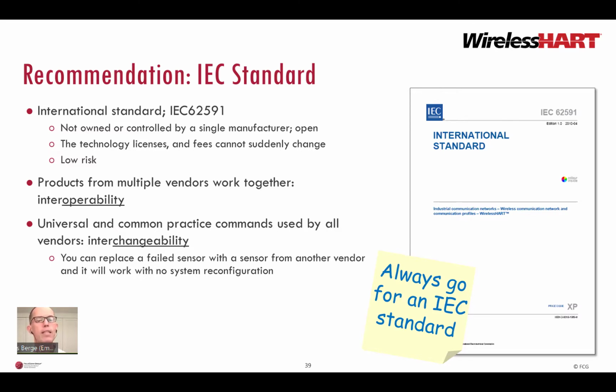Standardization dramatically reduces the risks associated with the technology. This is why I&C engineers specify IEC standards for all electrical and electronic equipment, including telecommunications, not just wireless sensor networks. Since there are technologies available that are an IEC standard, do not invest in other technologies which are not an IEC standard.